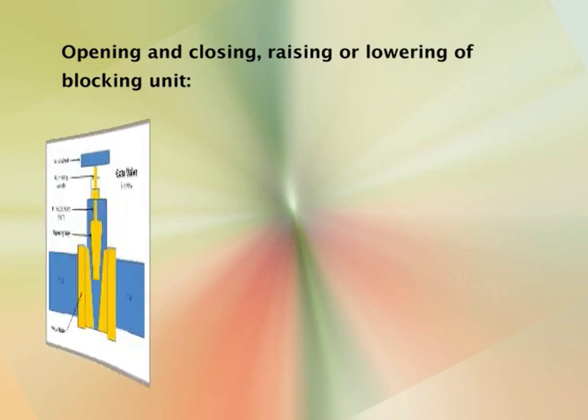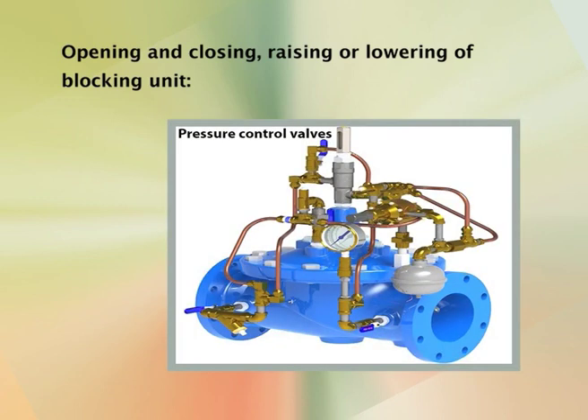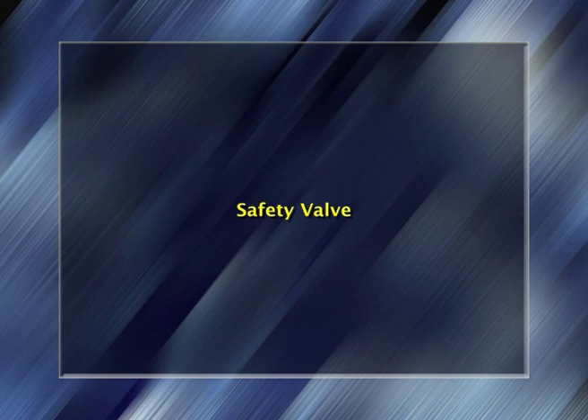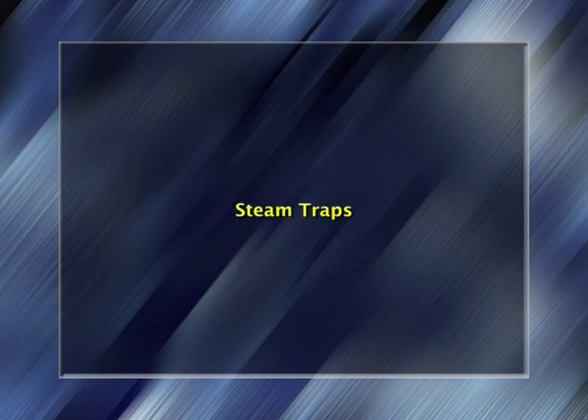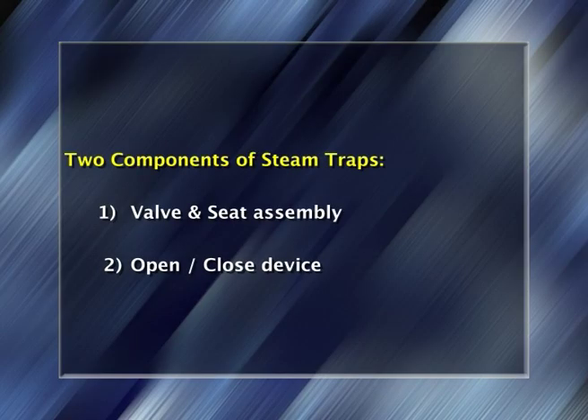Valves and steam traps: the different models of valves include gate valve, globe valve, piston valve, needle valve, check valves, and pressure control valves. Safety valve: there are two types by which increase in pressure is released — a spindle lifted from its seating against the pressure releases pressure, and bursting or rupturing of discs to release pressure. Steam traps are important to remove any steam condensate; they have two components: valve and seat assembly, and open-close device.